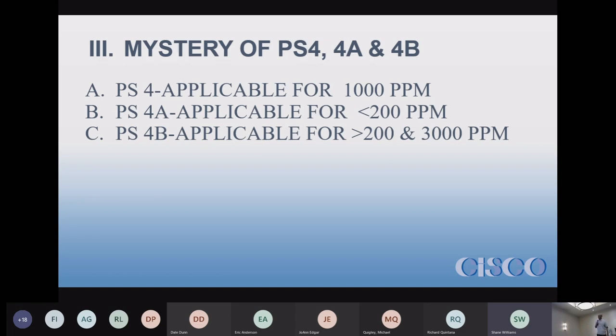Typically, performance spec 4 is for carbon monoxide. The issue we just recently ran into is that 4 is applicable for analyzers up to 1,000 ppm. 4A is applicable for analyzers less than 200 ppm. 4B appears to be for dual range analyzers, but their ranges are greater than 200 ppm and 3,000 ppm. Most sites have low ranges of 10 to 50 ppm at most, and then a high range can go anywhere from 200 to 3,000.